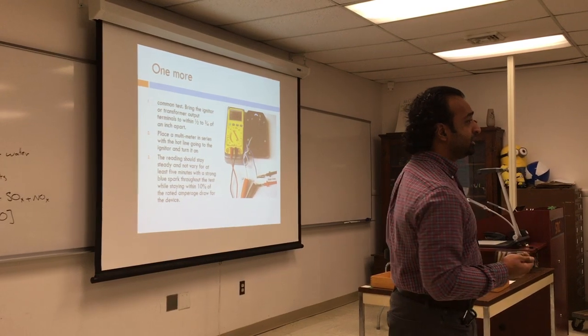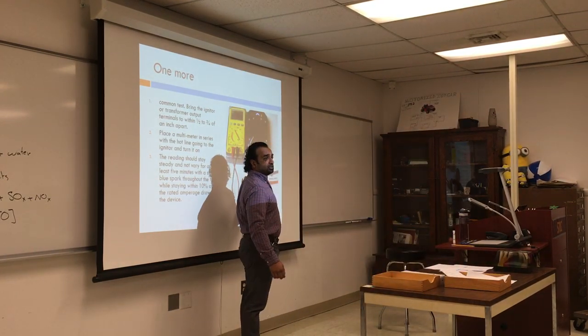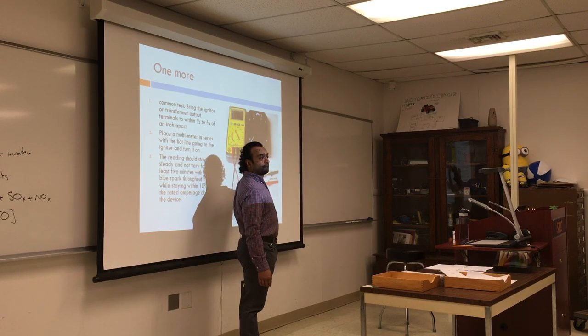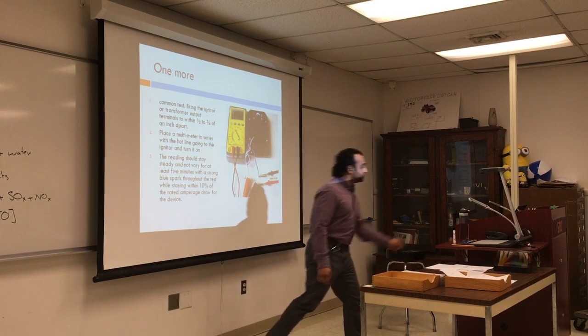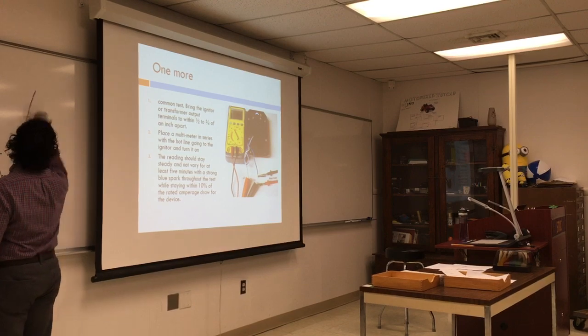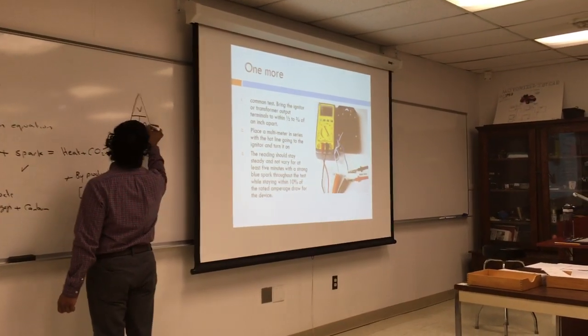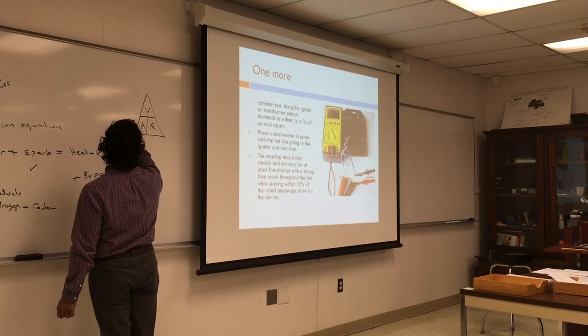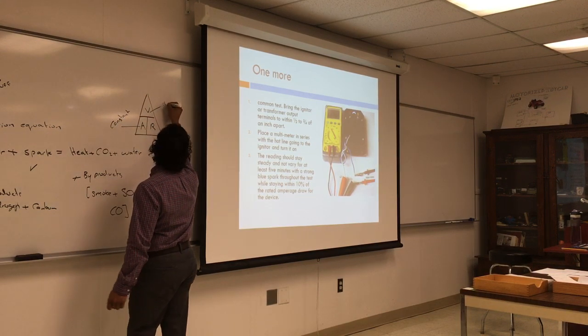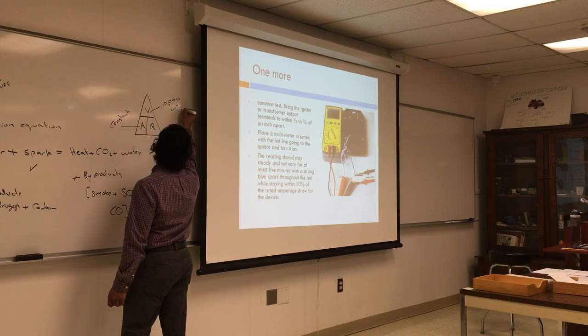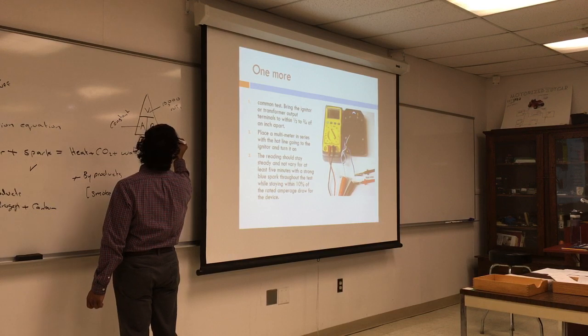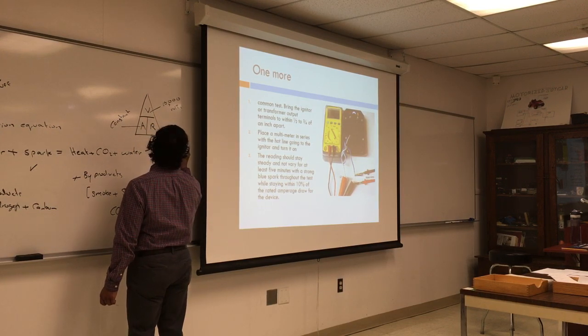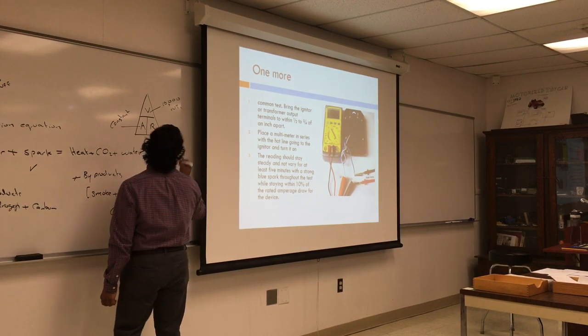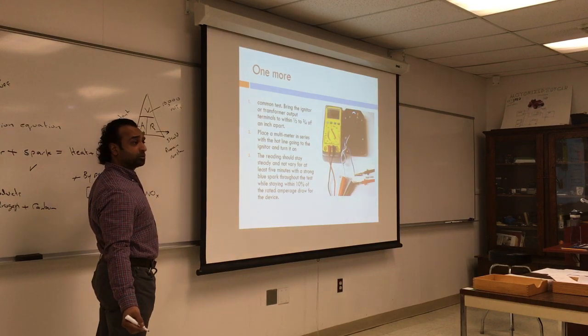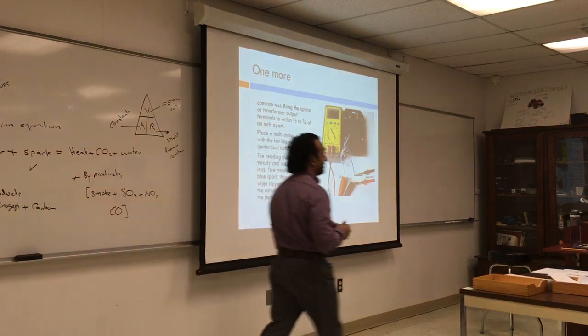Voltage over resistance. So if the resistance inside is sound, the amperage should not change that much. If the resistance is not as reliable or some of the wires are gone, after it heats up, it will probably drop the amperage. So going back to Ohm's law, if this is constant, and I have 10,000 volts here, this should remain. As the resistance changes, the voltage will change as well, and you can see the change by monitoring the amperage.